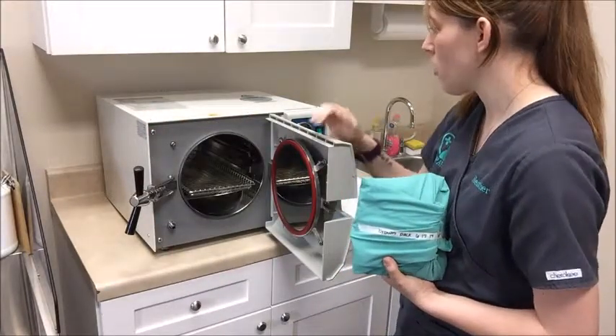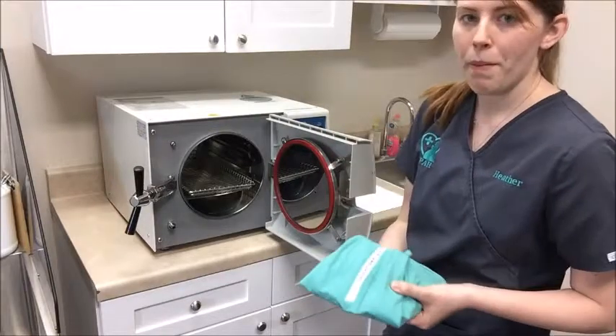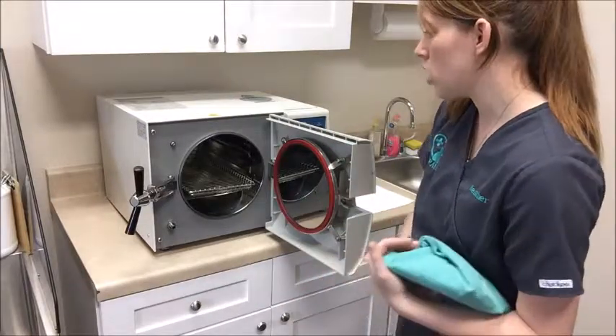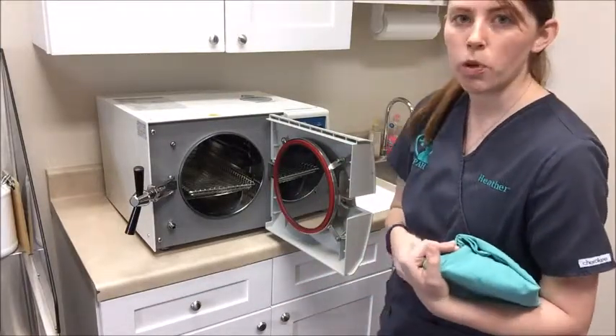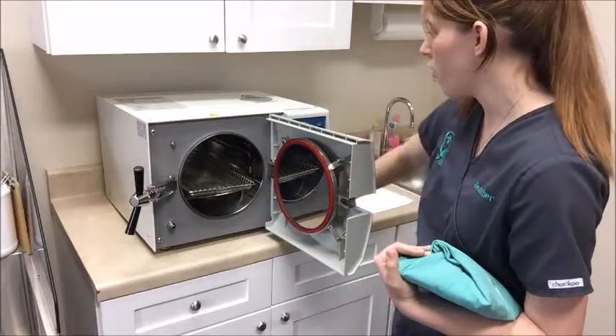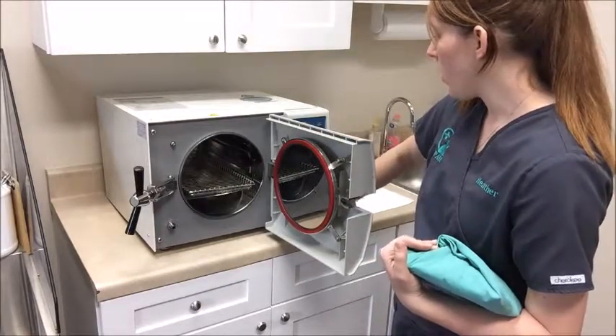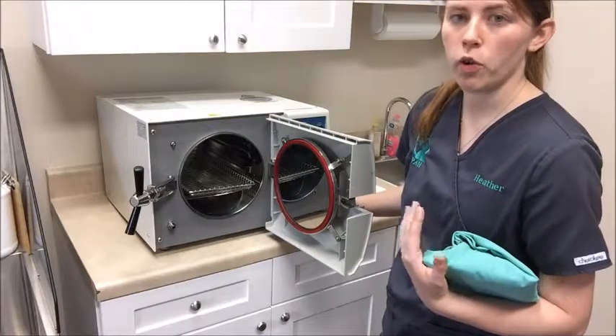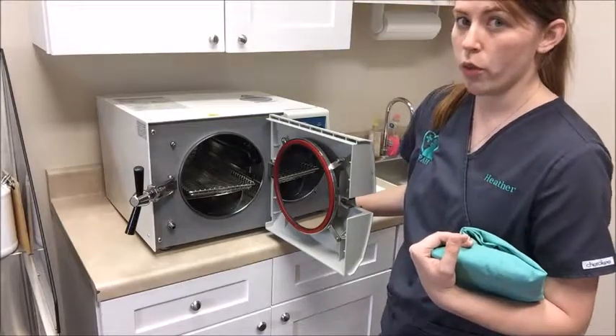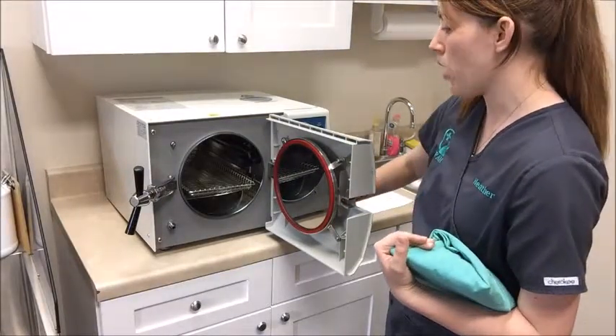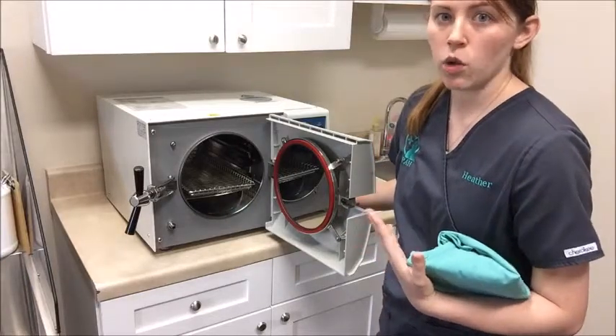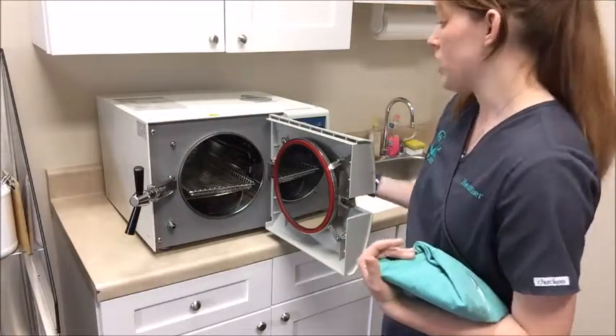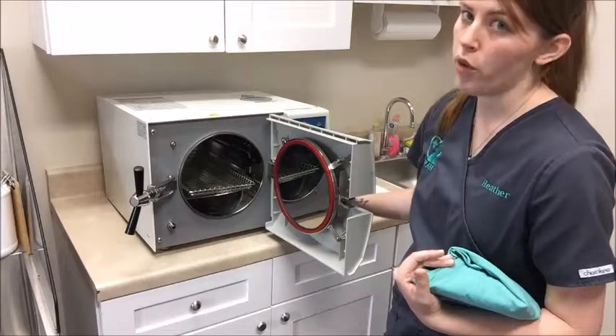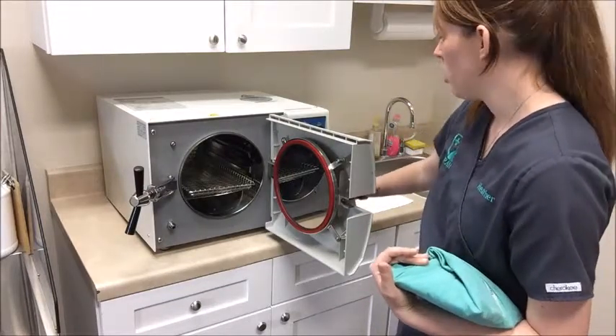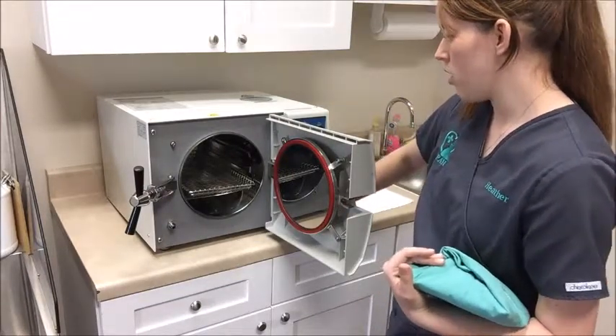So I'm going to fill this up with water. I'm going to wait to put my pack in just so I can see the water coming in and wait till it gets the appropriate line before I turn it off. And then it is important for my sterilization cycle to run for 30 minutes according to this model. And then once that 30 minutes is over, I'm going to manually exhaust the unit and then set it for a 30-minute drying cycle. So it's almost at the divot.